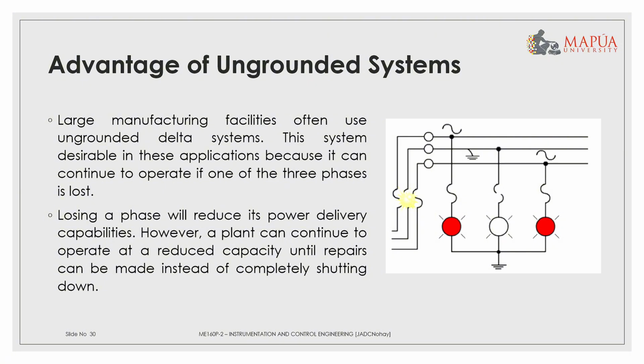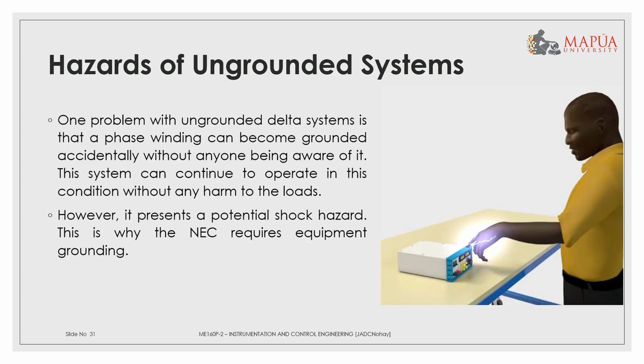Large manufacturing facilities often use ungrounded delta systems. This system is desirable in these applications because it can continue to operate if one of the three phases is lost. Losing a phase will reduce its power delivery capabilities. However, a plant can continue to operate at a reduced capacity until repairs can be made instead of completely shutting down.